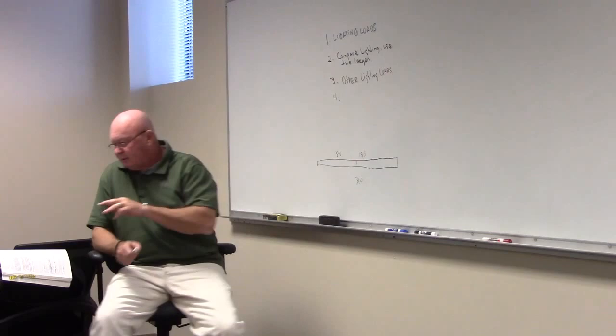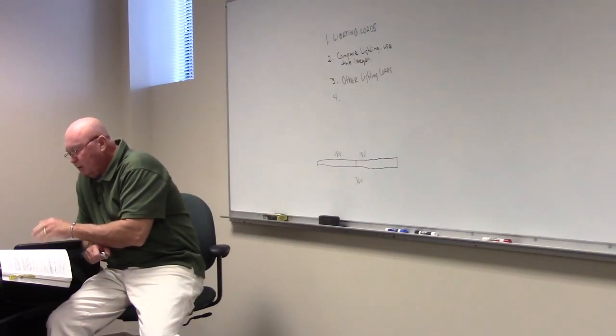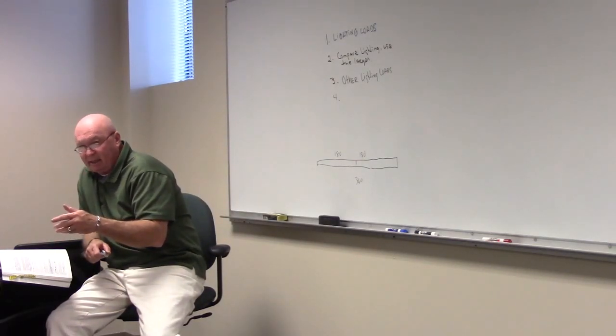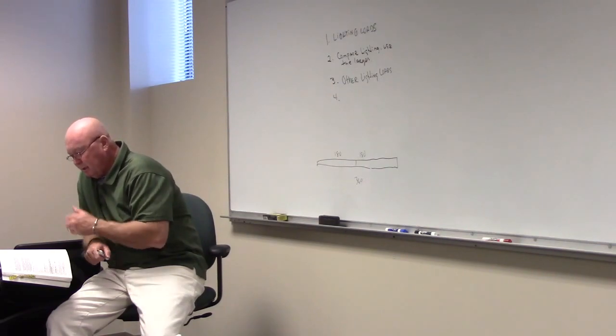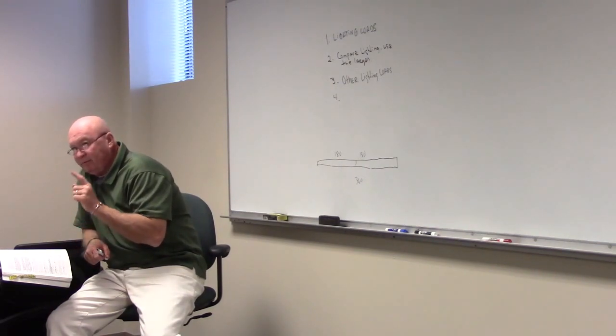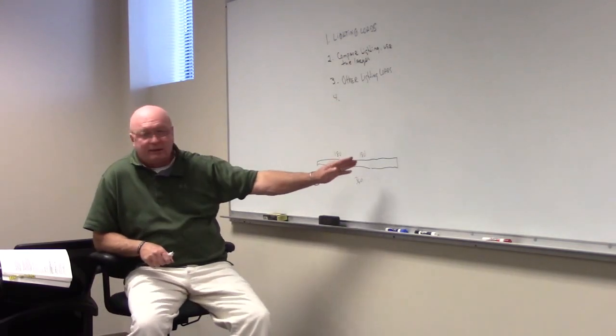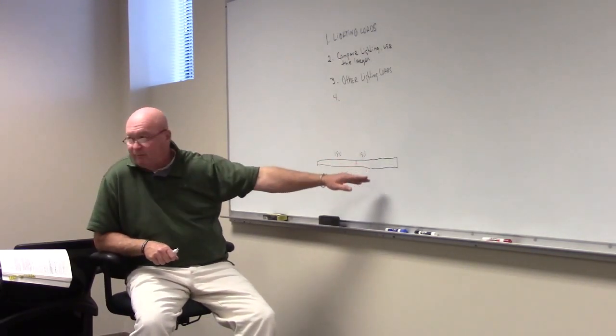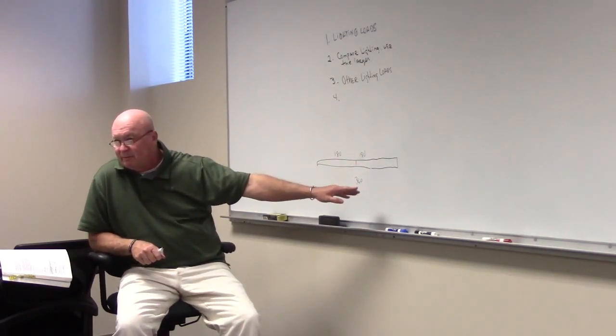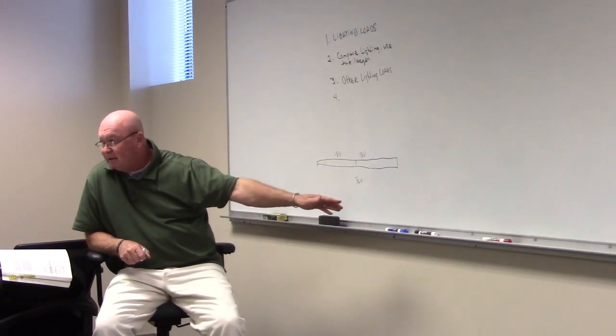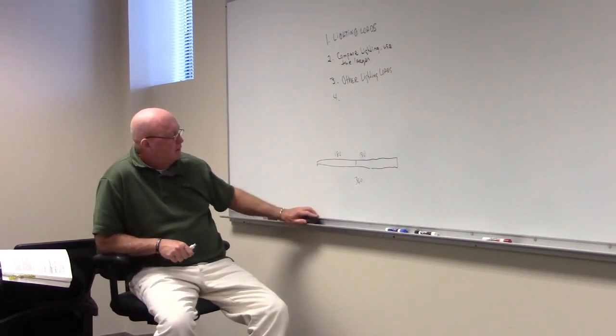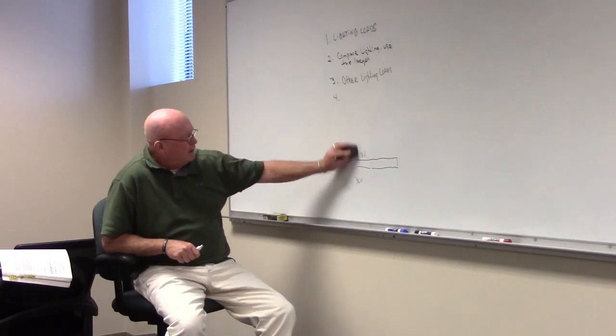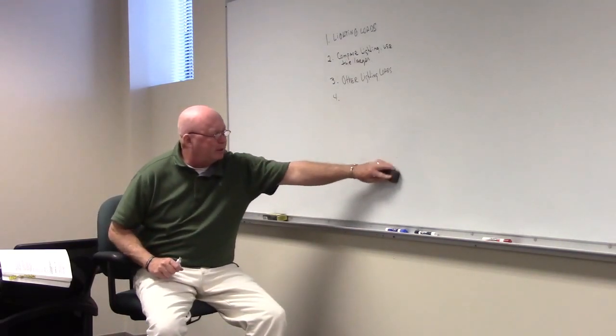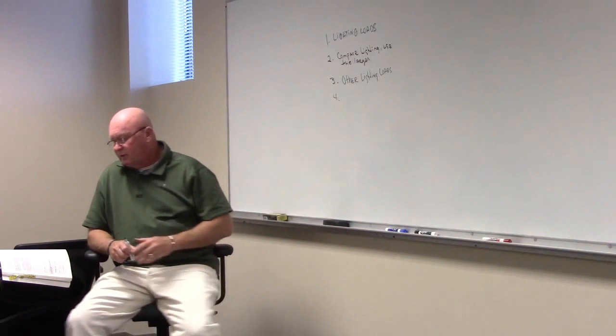Okay. Now that's if it's not, but look at number 2, where they would be used simultaneously, like maybe at a desk or something, possibly. Every foot counts in. So this 8 foot one then becomes 180 times 8, doesn't it? Big difference. That's the key. Are they going to be used simultaneously or not? So there's 2 different rules there.